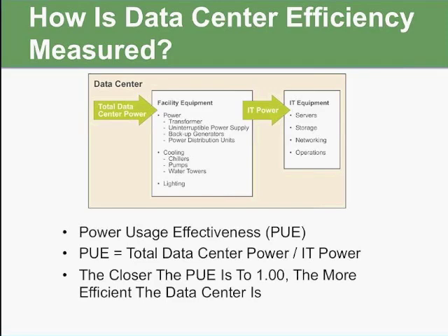That's PUE, and it basically takes the total data center power and divides it by the IT power. The facility end of that has everything from the power distribution units, the UPS, backup generators, the transformers that take the voltage down to the usable voltage for the IT equipment. It also includes the cooling. For large data centers, you've got cooling towers and chillers and everything else. For smaller data centers, you've got computer room air conditioners. And you've also got things like lighting that you should include in the total power.